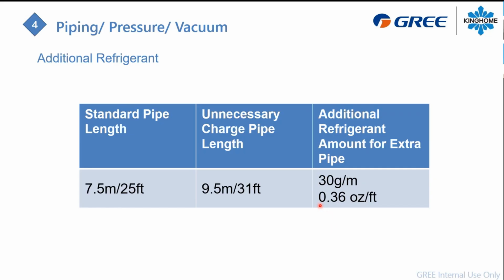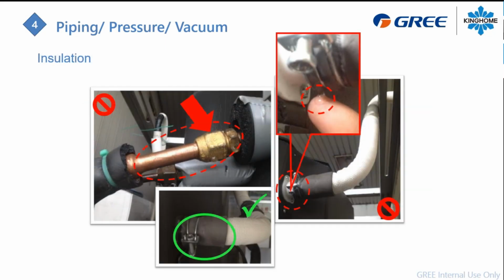So, 0.36 ounces per foot over 31. The insulation: only the suction pipe needs to be insulated. The 3/8 is a real liquid line, so it doesn't have to be insulated. If it is, it's okay. But if you do a retrofit and the liquid line is not insulated, that's perfect, that's good. We don't need to insulate it.